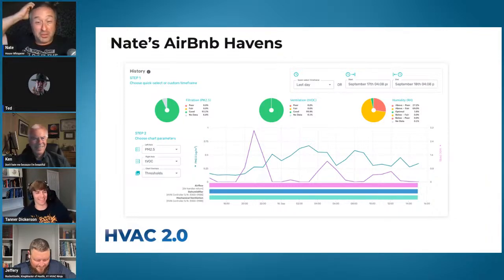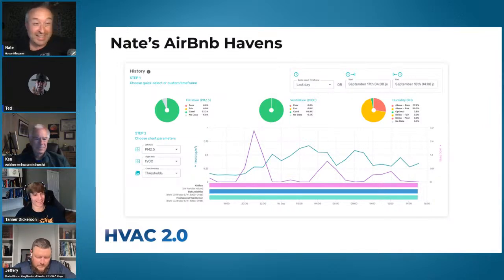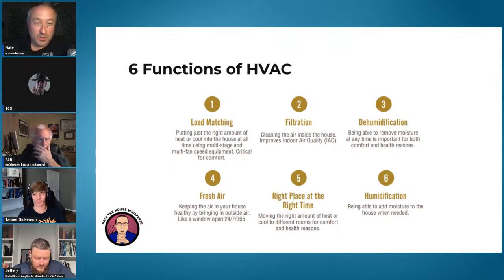The house next door, I don't think it ever realizes there's airflow happening. You want to talk about filter face velocity - we're trying to get it under 500, and at full speed it's like 70, and at low speed it's like 15. It doesn't get much lower than that. You can't even tell it's moving, which is a problem when you have an airflow sensor trying to understand what's going on. So yeah, it is what it is.